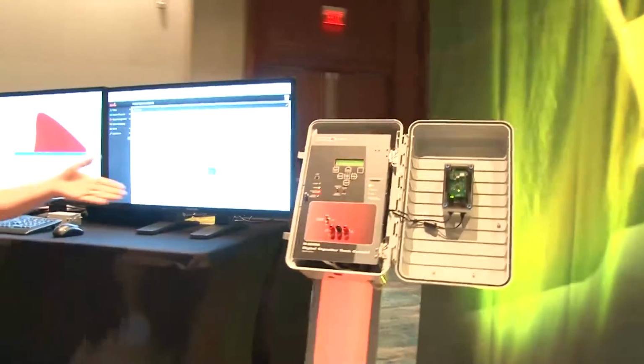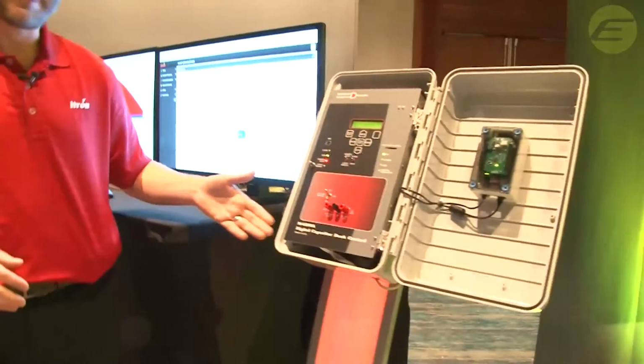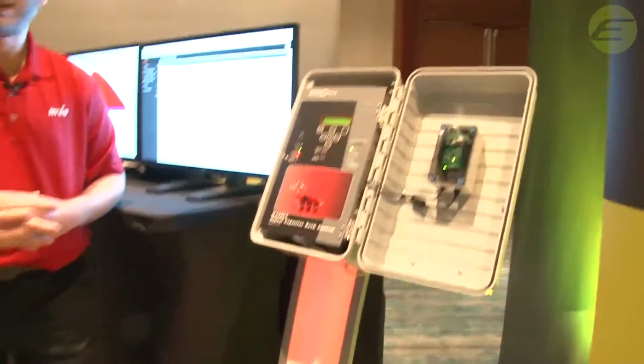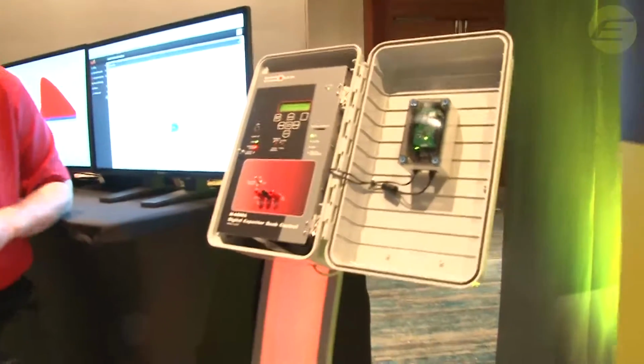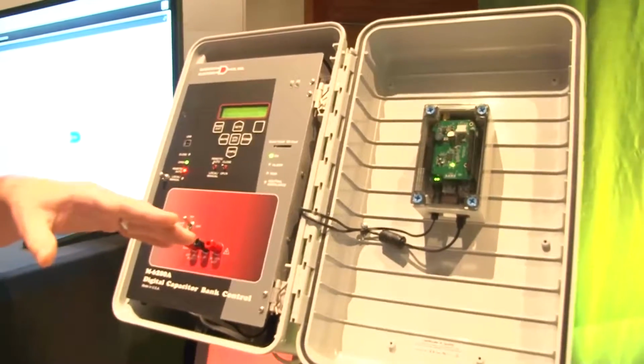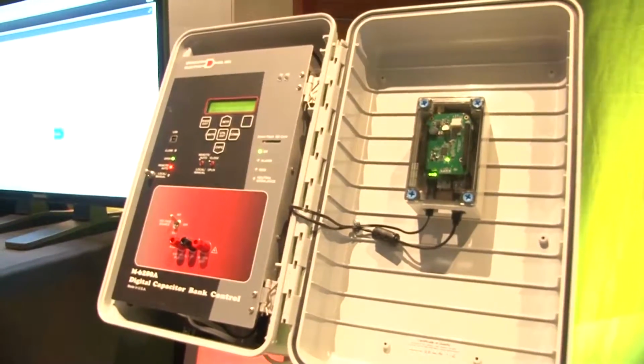So this is a cap bank controller. It's a distribution automation device. It's sort of an older model. It doesn't know anything about Riva or meshes or IPv6. But we've made it smarter with our Riva DA gateway here. Now, this is running a special application that is speaking Modbus protocol. And that's not a metering protocol. It's specific to this class of device. And so we can command it.